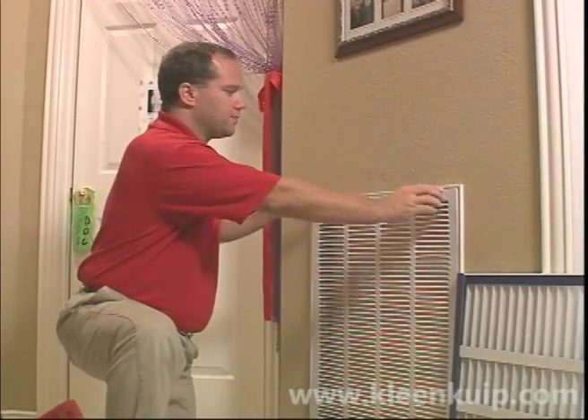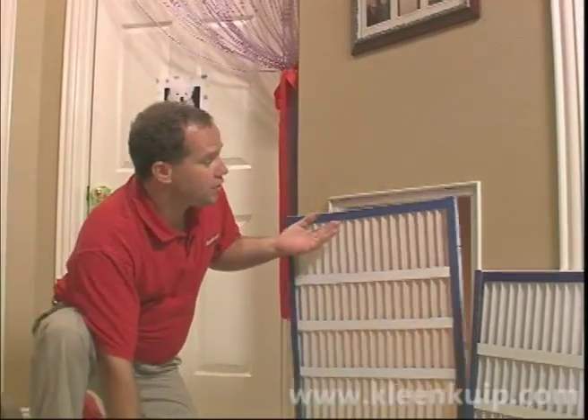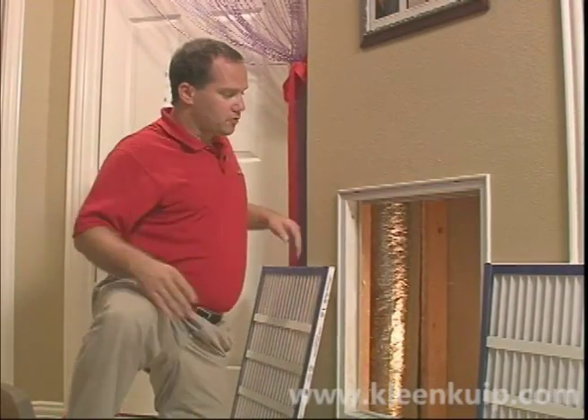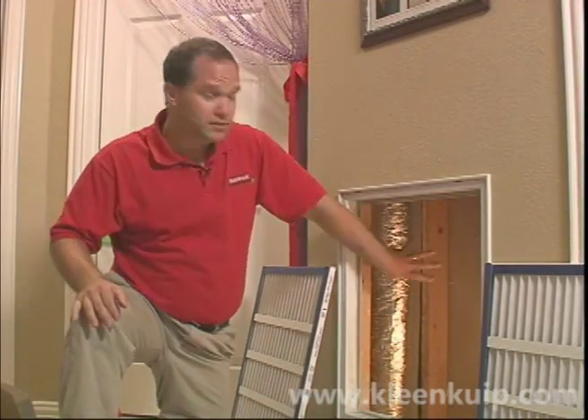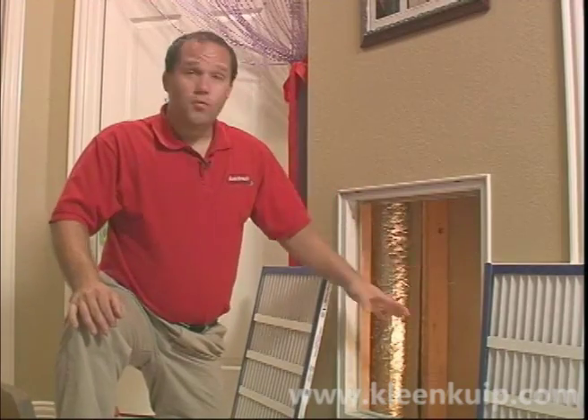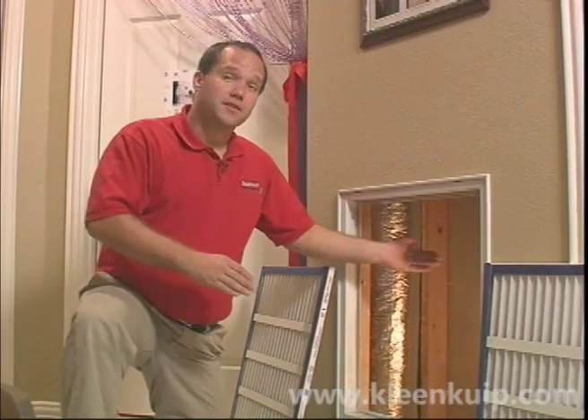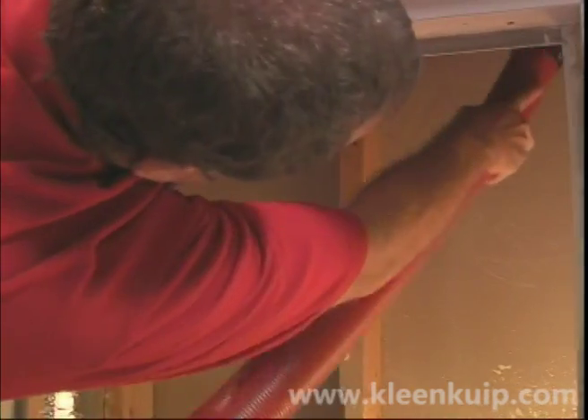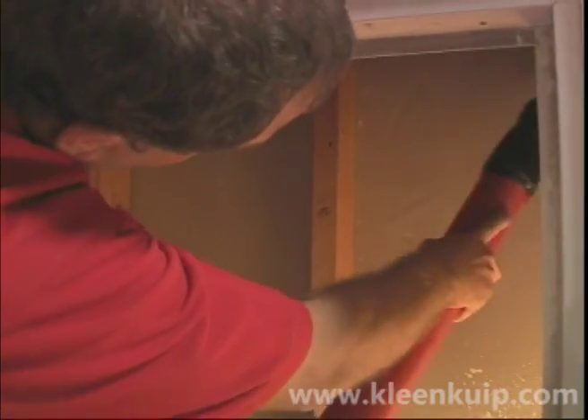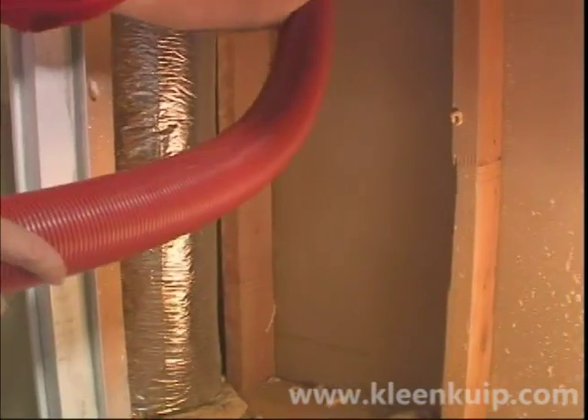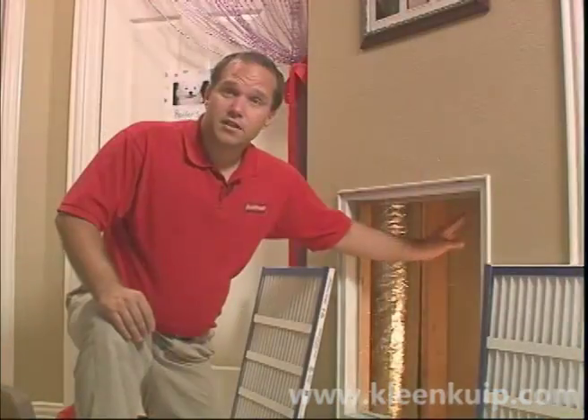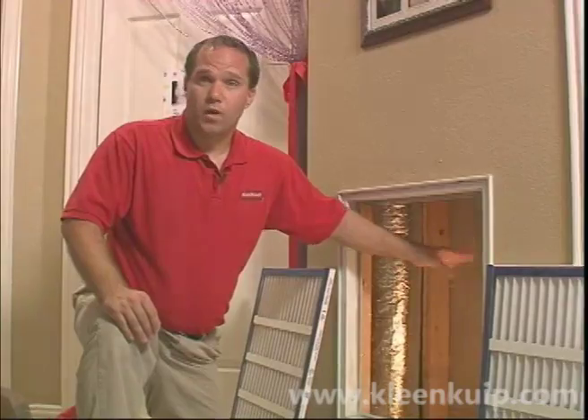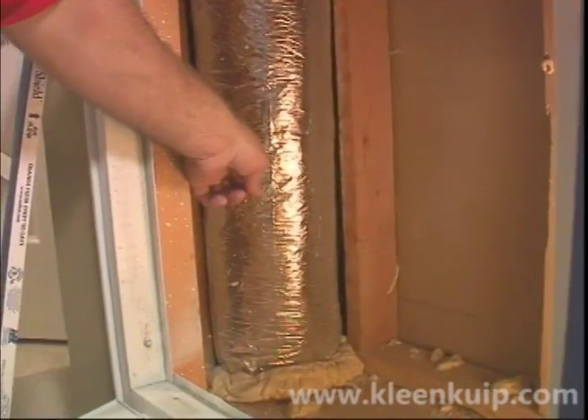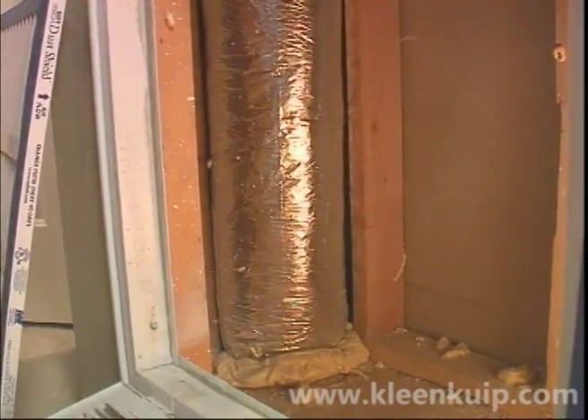Here's another return duct, and this is basically a wall chase. What that consists of is sheetrock and 2x4s. This one's exceptionally large, and you won't use a rotor brush in this application because of the size. You'll actually hand vacuum this duct. There are some wall chases that are narrow, about the width of a 2x4 with sheetrock, that you can use a rotor brush on. The other thing you want to be careful of is this can be used as a conduit for other items such as wiring, or in this case, ducting from the second floor to the first floor. So just be careful when working around these items.